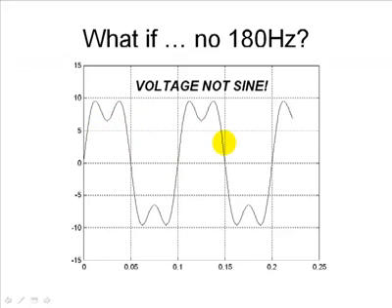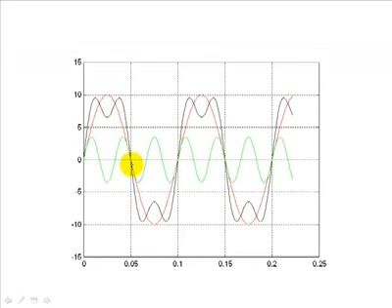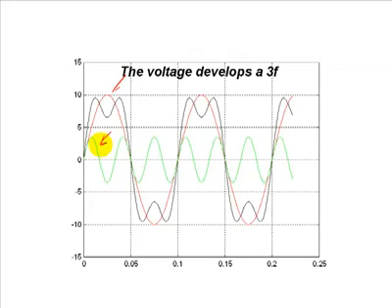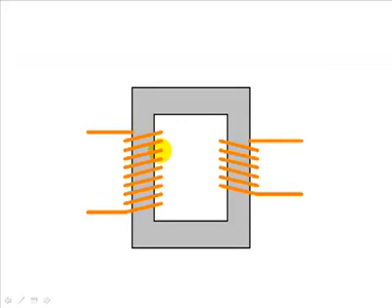It's not a sine. But interestingly enough, if we apply Fourier to that induced voltage now, which is seen, by the way, by the customer, we realize that voltage is the sum of two sinusoidal voltages. One voltage of 60 Hertz, this one, and one voltage of 180 Hertz. That is, now we do not have triple frequency in the magnetization current, but the price we pay is that now we have a triple frequency voltage, which is visible by the client, by the customer, and that is not good and not acceptable.